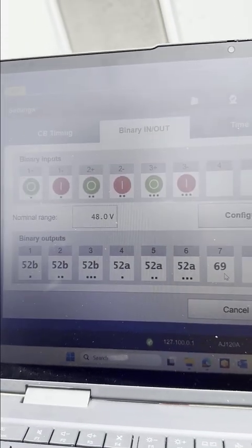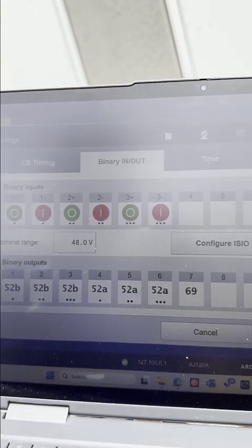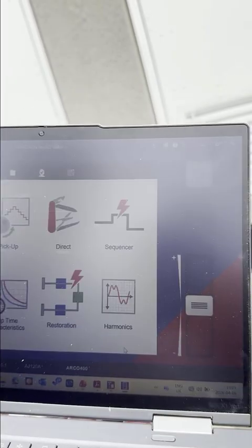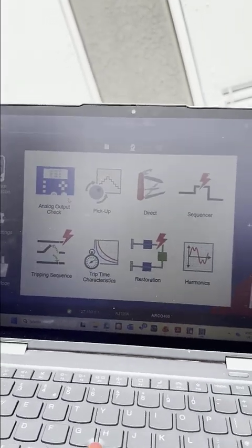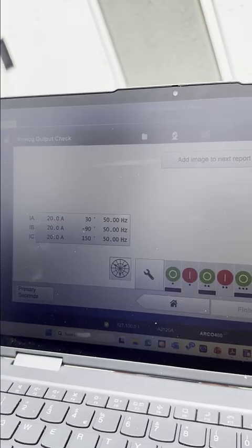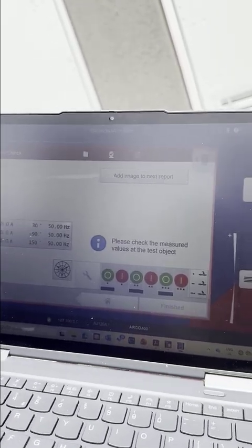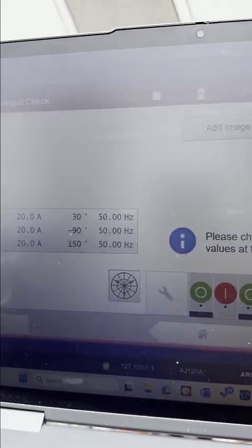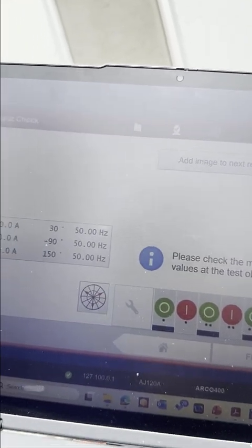And here is the binary output, which indicates the 52A and 52B, which is the circuit breaker status indication, and also 69, which is the yellow handle status. Then you can click apply, and here you can specify the analog output check, just to make a wiring check, as you can see. So now I'm injecting 20 ampere in primary, and also you can select here the display option to be displayed in primary or in secondary values.